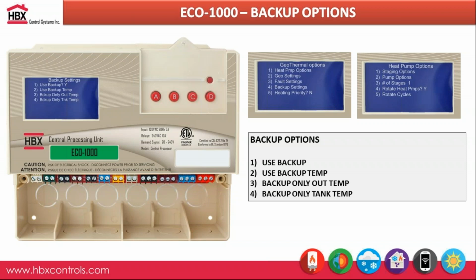You have the option to use the backup boiler only. This will lock out your heat pumps if you select this option, and that comes off of temperature as well. Say I only want my backup boiler to be operating at minus 10 degrees Fahrenheit, because I really don't need my heat pumps firing up. My backup boiler can do everything on its own, so it'll lock out the heat pumps and just run the backup. Or you can have the backup come on based off of tank temperature.